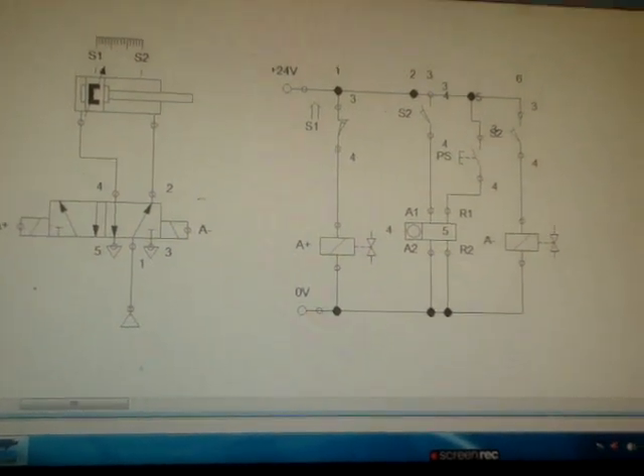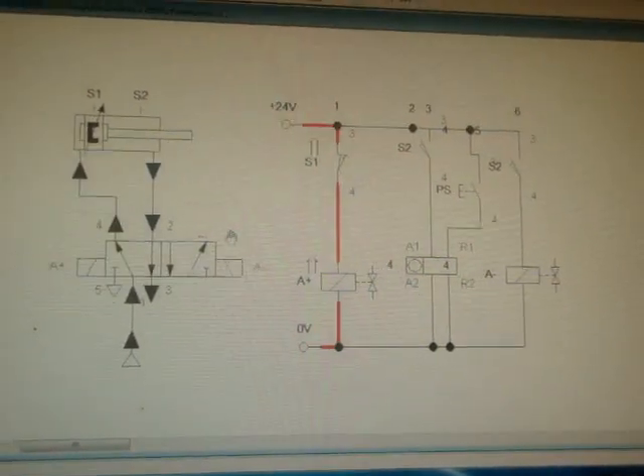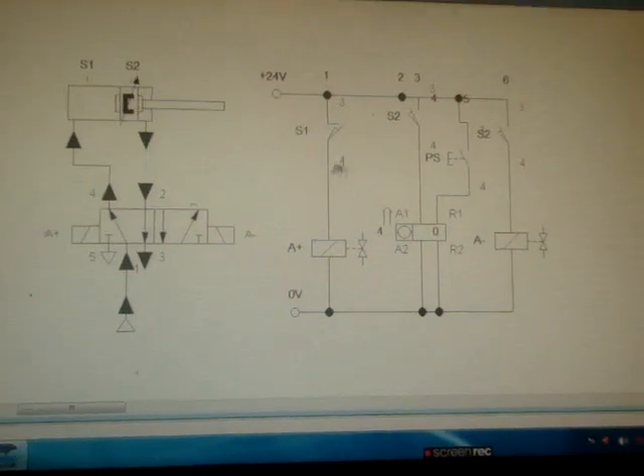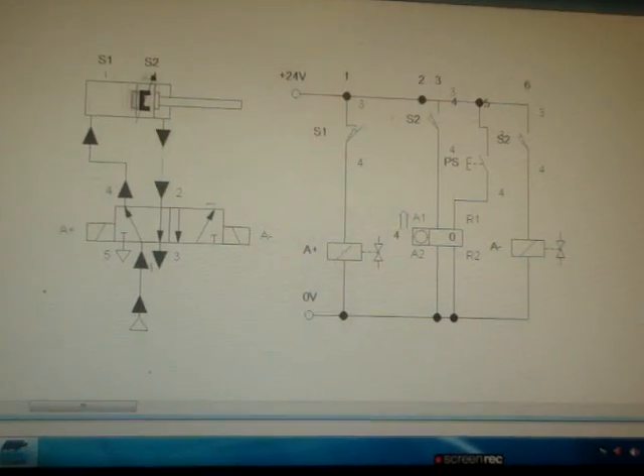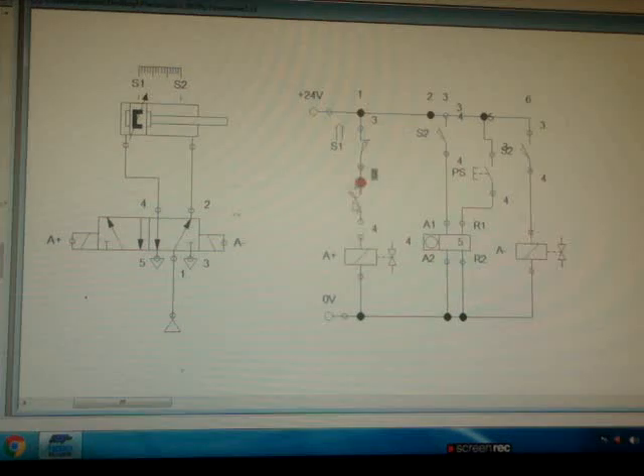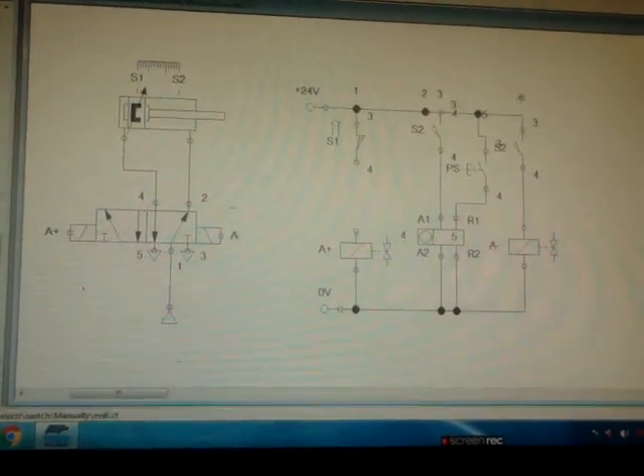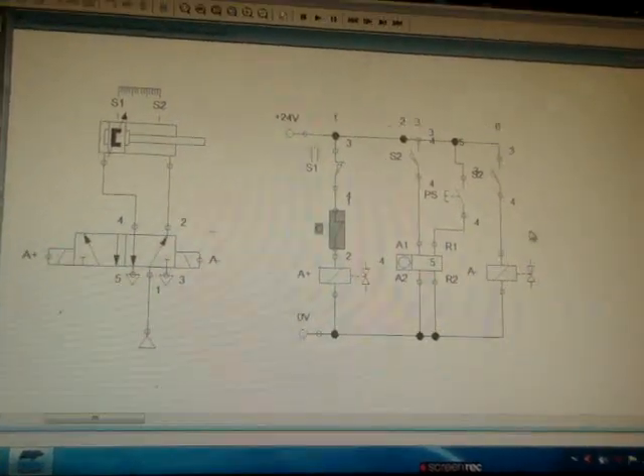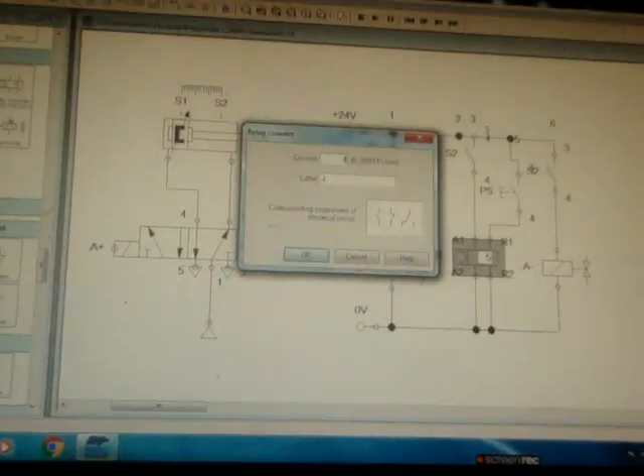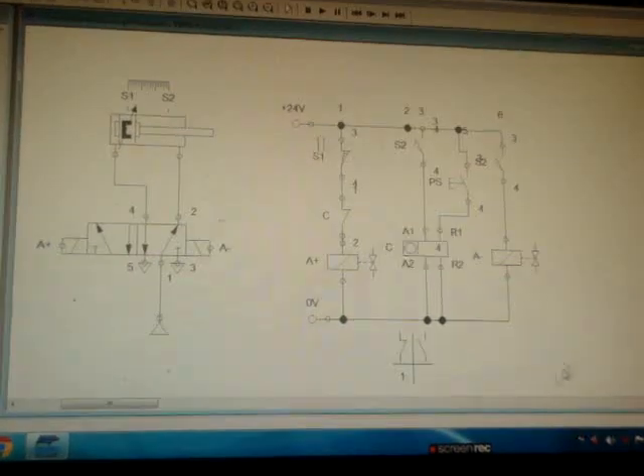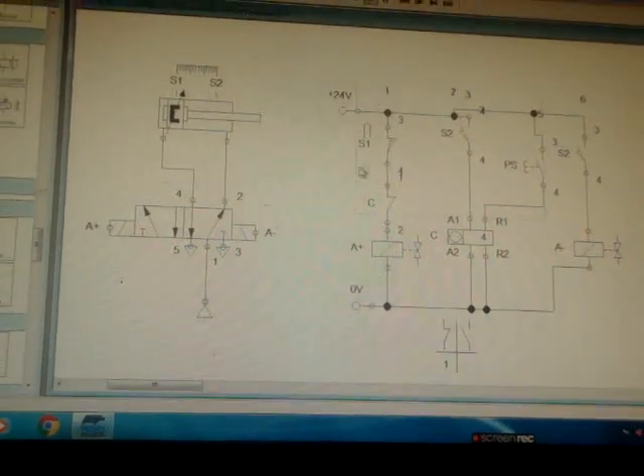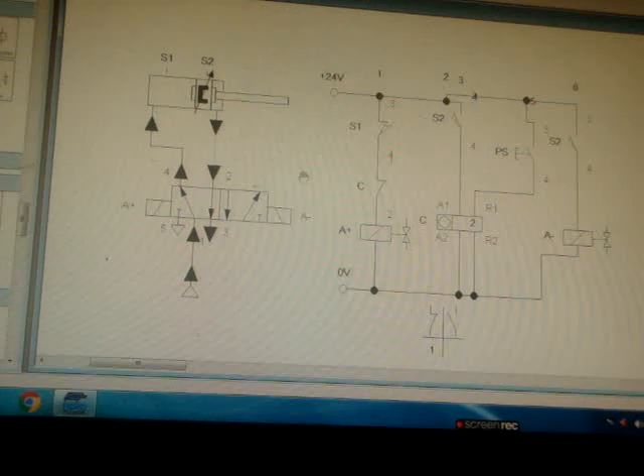Now you see how it works — I will run the animation. One, two, three, four. I have not given the interlocking so after four it is still moving. I need to add a normally closed counter contact on the A plus line to stop it when the counter is on. I will set counting to four and name this counter C. Now you see it is working properly. One, two, three, four.